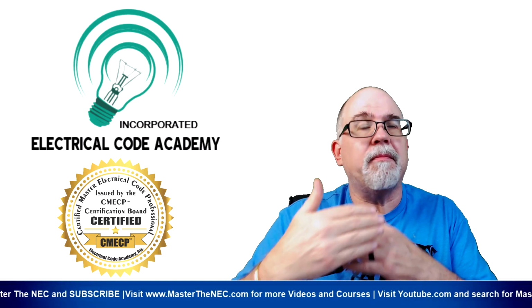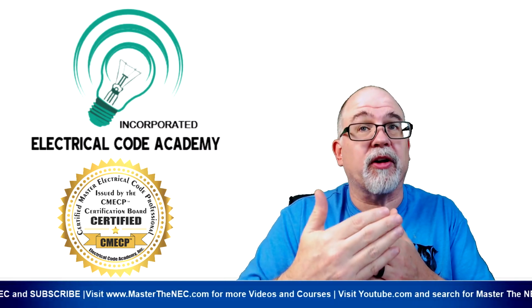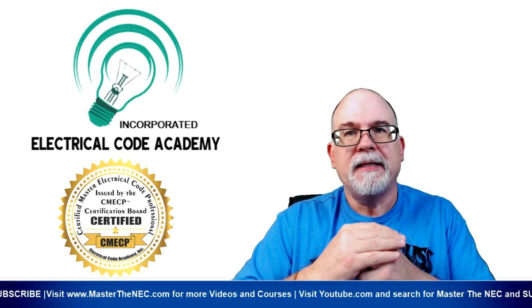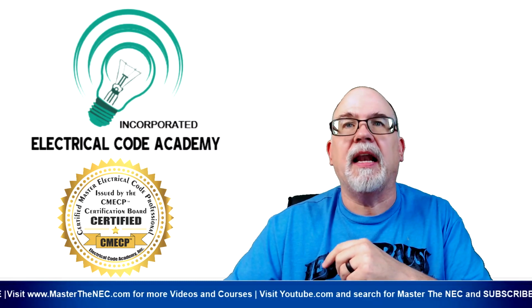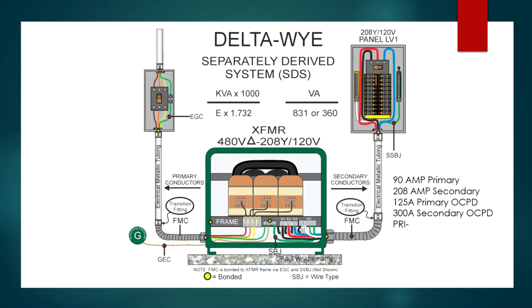So on an exam, if it asks you for that, you're going to go up to the 125%. But in the real world, if it's a 200 amp device, let's look at the graphic. That way I'll make it a little simpler. If this right here was 200 amps, then these conductors right here that terminate into it would have to be rated for 200 amps, and that would be a 3/0 copper. Again, we're always assuming copper unless stated otherwise. All right, and so that would be the design, and this transformer could handle this with no problem.